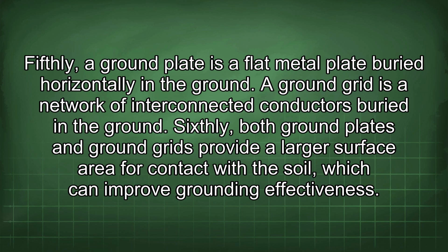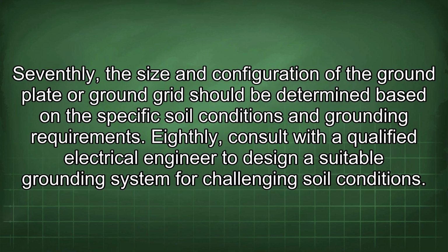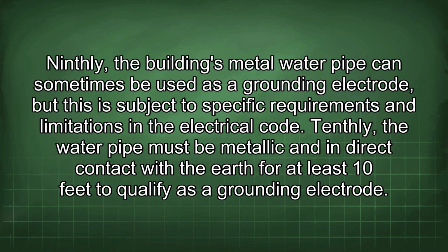grounding effectiveness. Seventhly, the size and configuration of the ground plate or ground grid should be determined based on the specific soil conditions and grounding requirements. Eighthly, consult with a qualified electrical engineer to design a suitable grounding system for challenging soil conditions. Ninthly, the building's metal water pipe can sometimes be used as a grounding electrode, but this is subject to specific requirements and limitations in the electrical code.